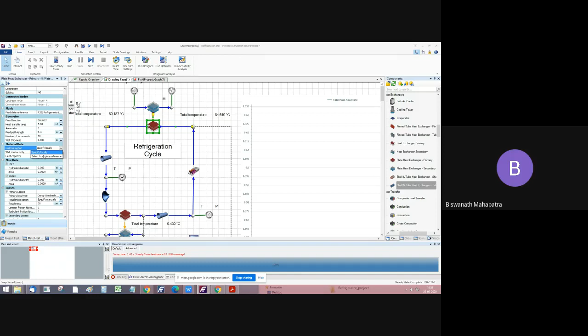Here we are specifying inputs like the heat transfer area, meaning the surface area of the plate type heat exchanger. Then the fluid path length, which means how much distance the fluid covers while it is transferring heat to the secondary side. Then the number of increments means it will divide the total length into 20 incremental lengths and calculate at the 20 points. Then wall thickness, then the material option: we can specify our wall conductivity and heat capacity if known, or we can select the specific material from the material library according to our need.